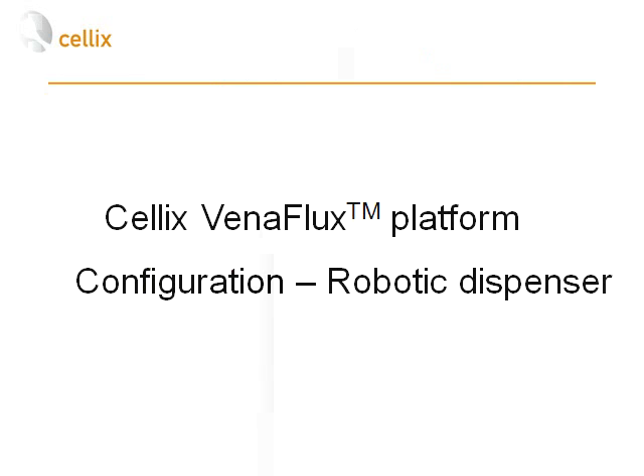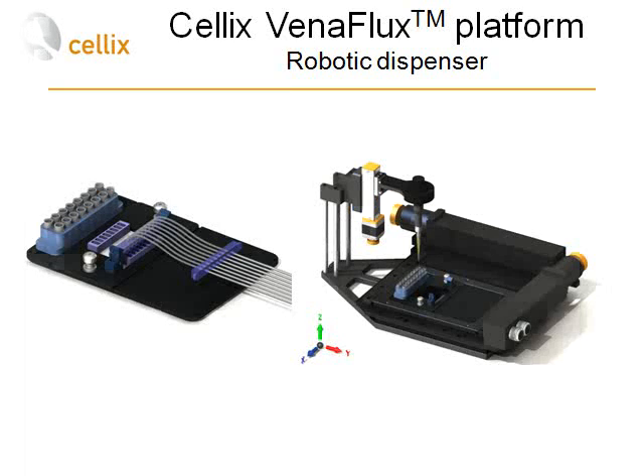There is also an option to have robotic dispensing. If you would like to transfer samples not manually but automatically from Eppendorf tubes or 96-well plates onto a chip, we have an option of a robotic dispenser arm — a single pipettor. It can perform simple functions like re-suspending cells in Eppendorf tubes, transferring cells from one Eppendorf tube to another, or from an Eppendorf tube onto the well of the biochip.